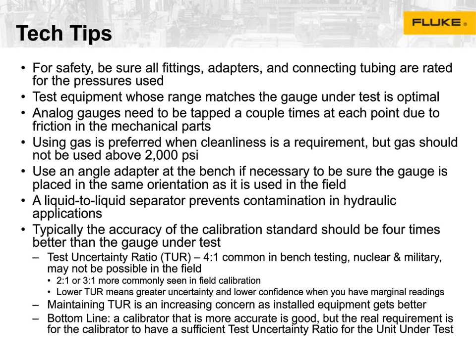Basically, when you have a lower test uncertainty ratio, a TUR of, say, 3 to 1 or 2 to 1, what that means is that when you get an out-of-tolerance reading, you have less confidence that it's really out of tolerance. And so frequently, the best way to deal with that is to use a different setup and have someone else try to do the calibration. If you do 2 calibrations at, say, 2 to 1 or 3 to 1 with different setups and they're both out of tolerance, it's more likely that the unit is actually out of tolerance rather than you just had a bad calibration. So that's one way of dealing with it.